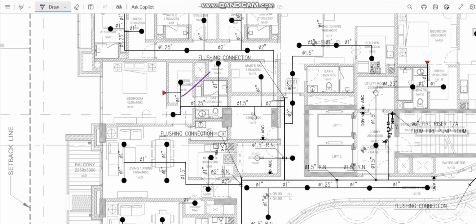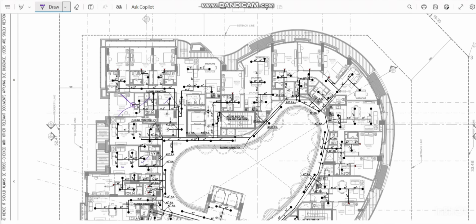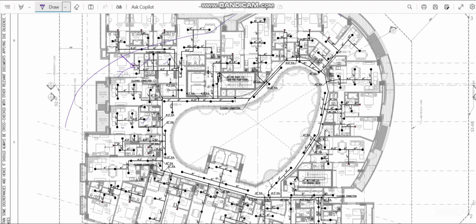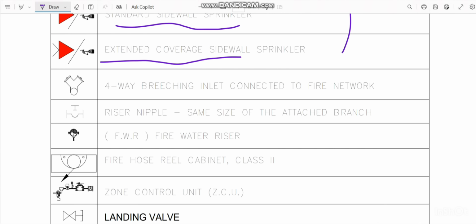But coming to the bedroom, we don't have a ceiling. Because of no ceiling, if we install an upright sprinkler, it will look very ugly. So that is the reason we installed the sidewall sprinkler here. This will protect the complete area, and the maximum coverage has also been verified. Also in the maid room we have installed the pendant sprinkler. So overall for the apartment, mostly we have used the pendant sprinkler. Only for the bedroom, because of no ceiling, we have used the sidewall sprinkler.